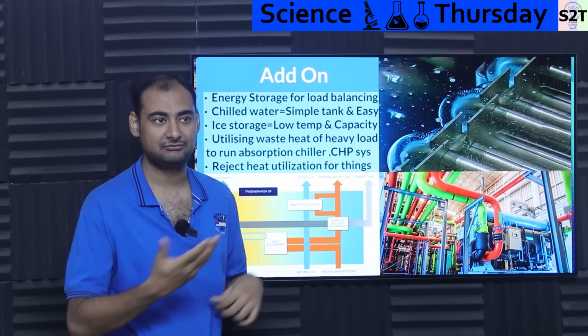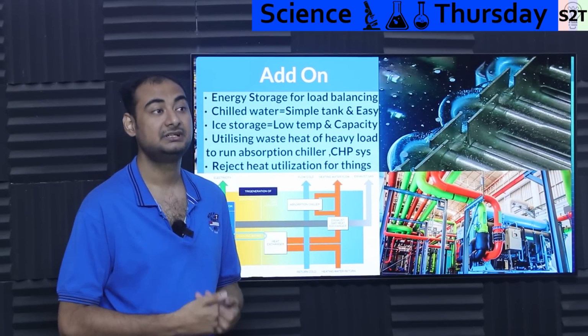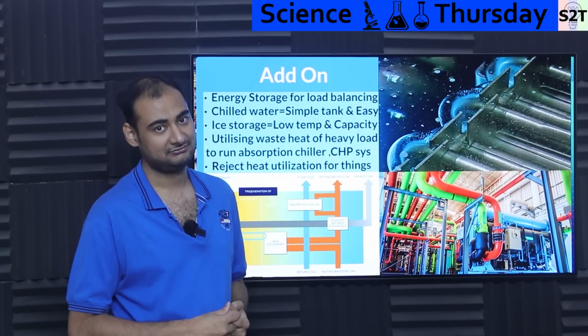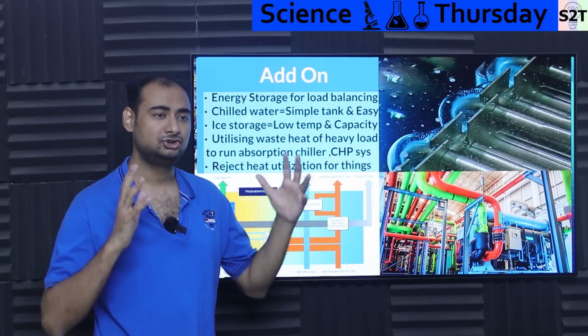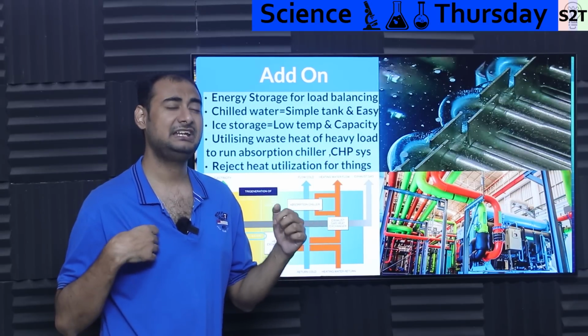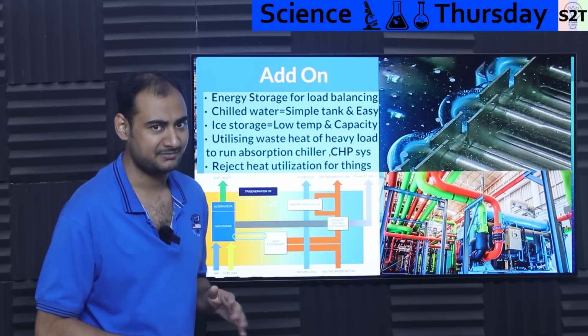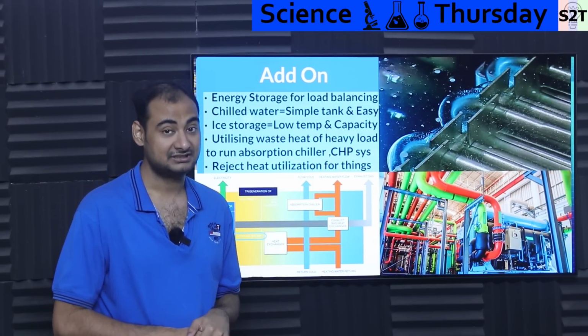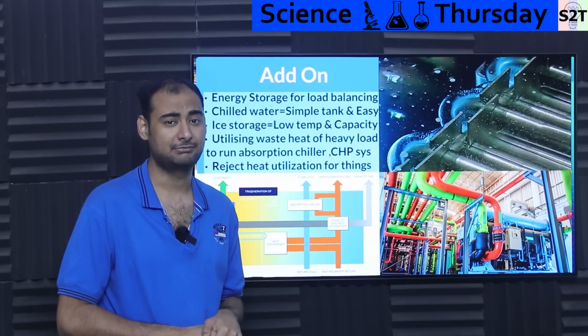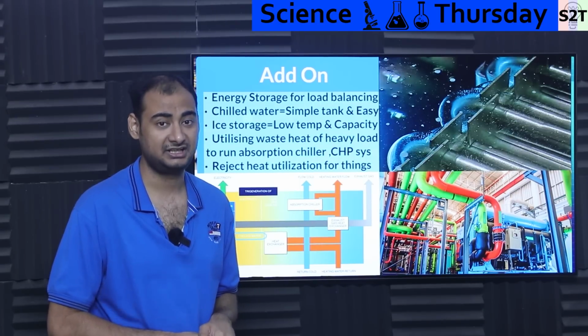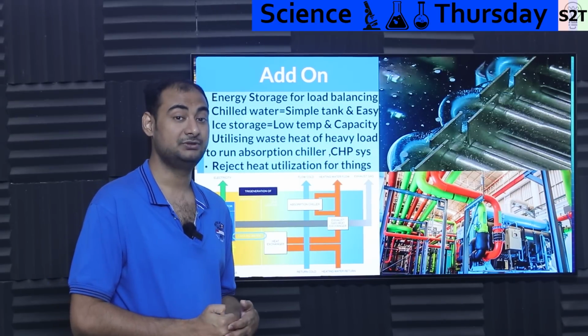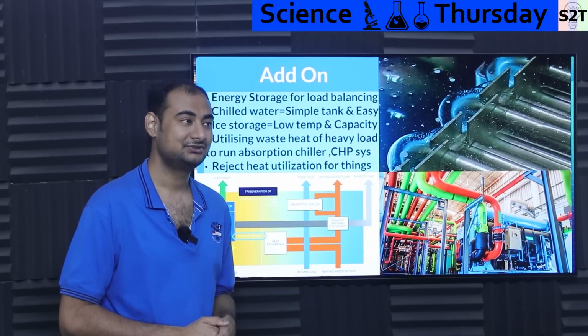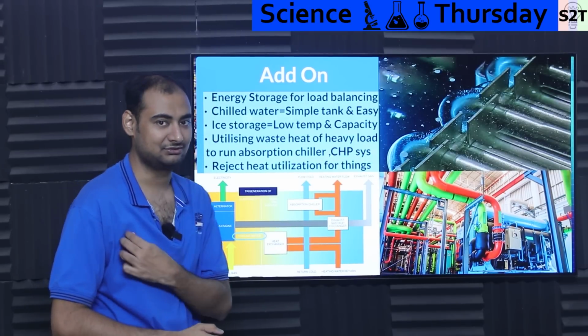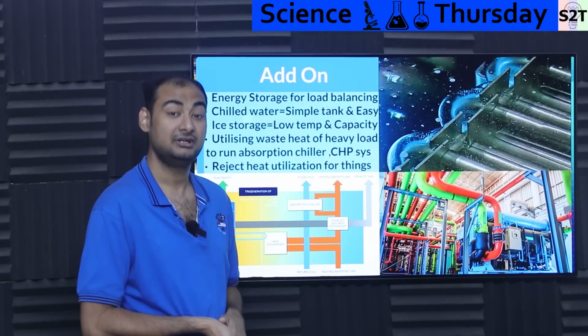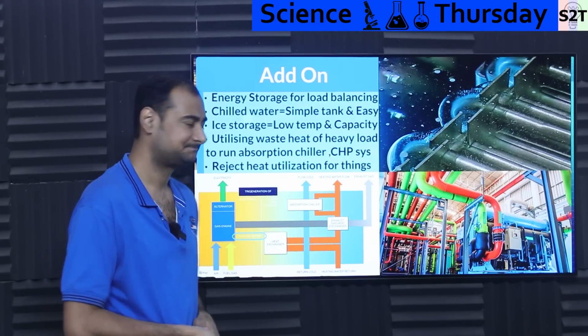Generally the reason we don't use fire to do refrigeration is the COP is very poor. With an absorption chiller, you dump 2 gigawatts of waste heat, and if you're lucky, you get 900 megawatts of cooling. Compare that to a compressor on electrical energy, which gives a COP of 3 on a bad day, 5 on a good day. It's non-comparable - that's why we don't burn fuel to do refrigeration. We used to, but electricity became cheaper.